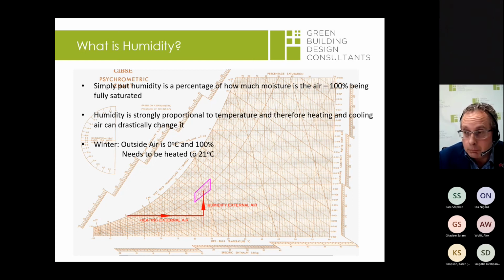If we were mixing that with return air from the space, which would likely have higher humidity because there are people in it, those two conditions can mix and the humidity rises. That's where, in modern design, you'd look to raise the humidity of your fresh air.